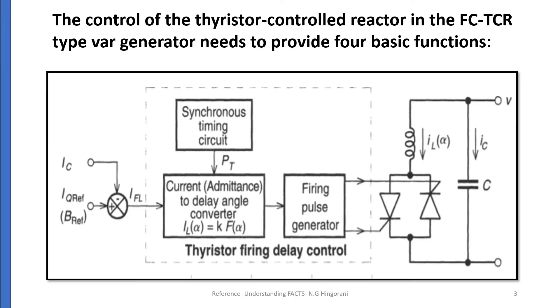Here we can see in this diagram this is our FCTCR. IC is a fixed current, wherein IL of alpha is varied by controlling the firing pulse. The required reactive power of the system is provided by controlling the reactive power of this TCR unit.